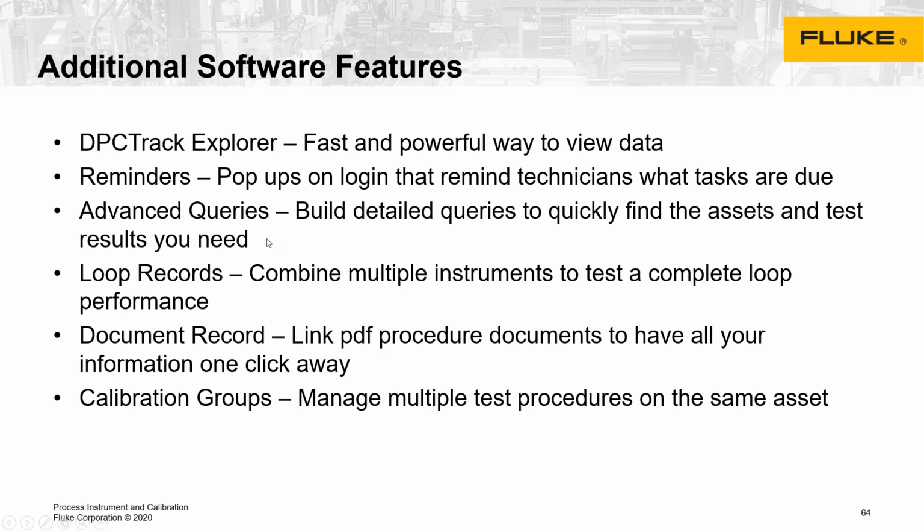Advanced queries allow you to build and pull data from different locations, really dig into your data mining for better fault isolation. A great example of that would be a customer looking at the number of times the serial number on an asset changes, as a good way to indicate how many times they actually have to change the transmitter. Certain manufacturers are being changed more than others in certain services. They could use that to identify maybe that they're having a problem with a certain brand or make of transmitter.